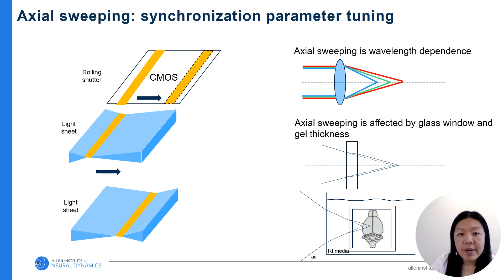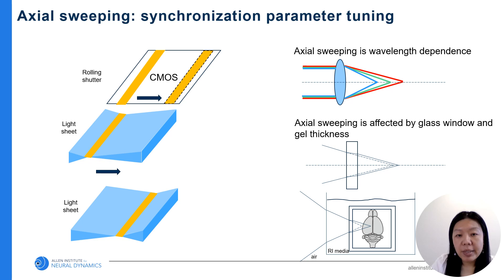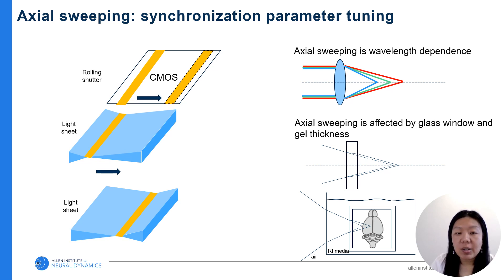Several factors affect the synchronization. It seems straightforward: when the ETL focuses the beam on the left edge of the imaging field, the rolling shutter starts at that edge and stops at the other. But in reality, the ETL has mechanical moving parts and the real focus-shifting curve has some lag relative to the input control signal. Also, chromatic aberration of the ETL, the thickness of the glass window, and the gel surrounding the tissue can affect the focal plane of the beam. Carefully tuning the parameters of the ETL control signal is very important for good synchronization.